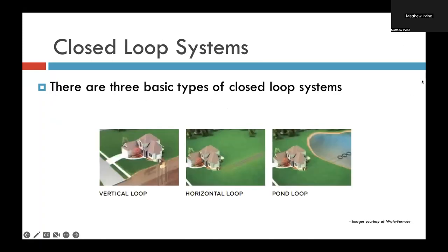There are three basic types of closed loop systems. There's a vertical loop, which, as the name suggests, you're installing the loop vertically into the ground. There's a horizontal loop, which, as the name suggests, as opposed to going very deep vertically, you're going horizontally, which requires more land. And then a pond loop, which is basically a closed loop that takes up a smaller footprint than a horizontal loop, but does require a body of water.